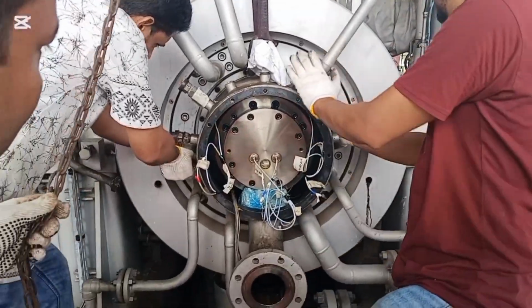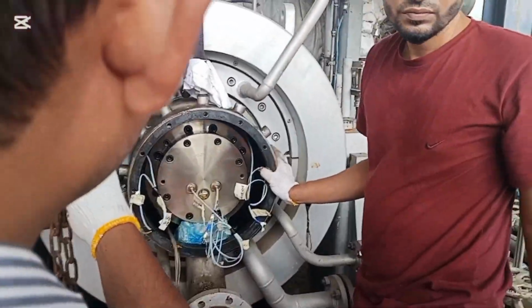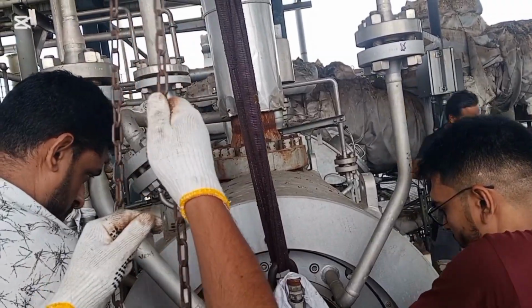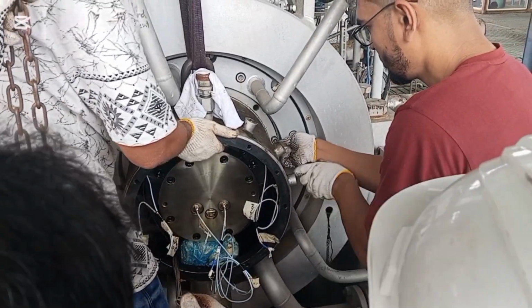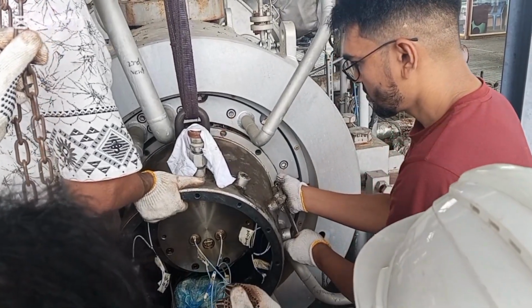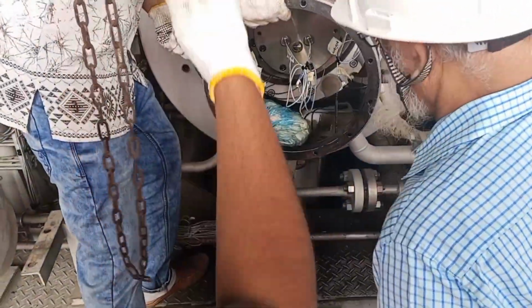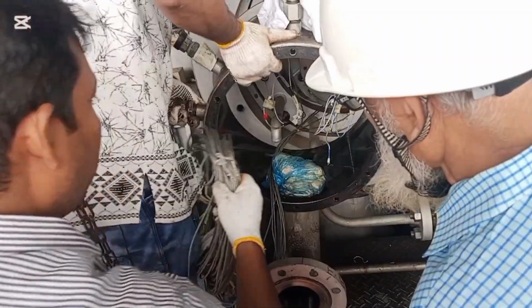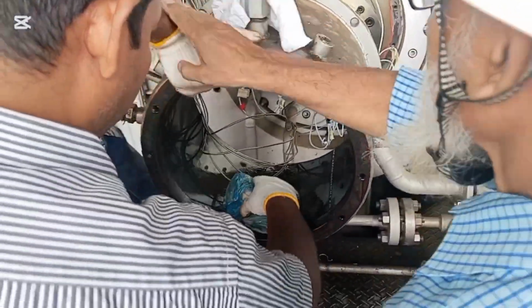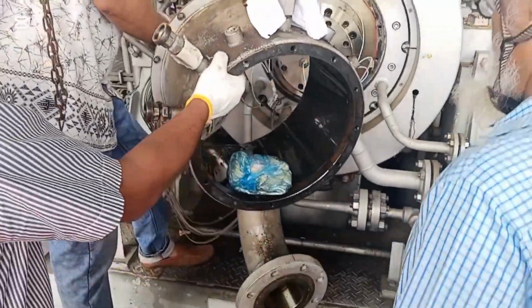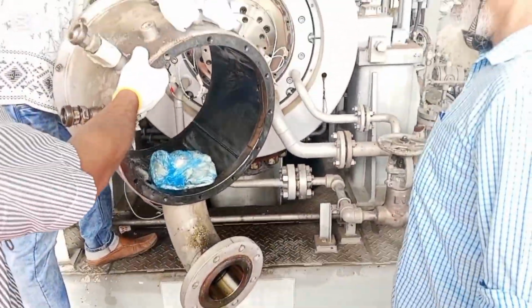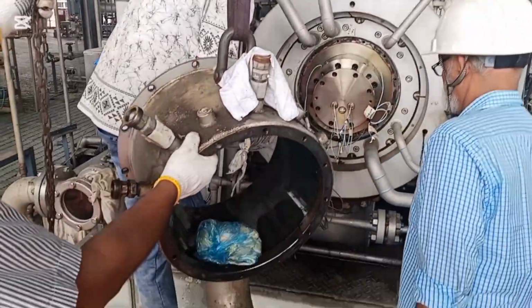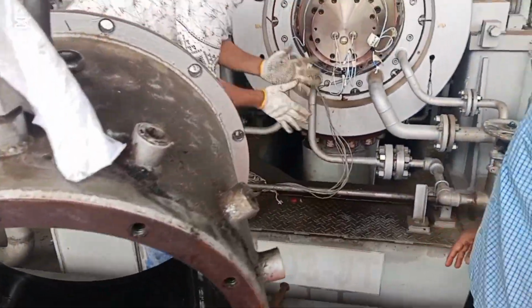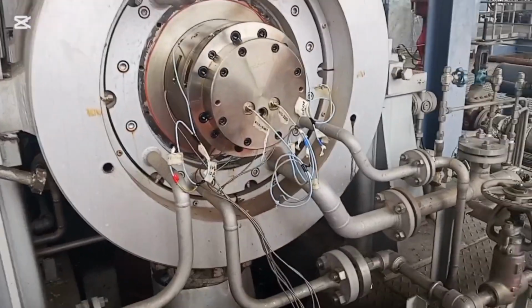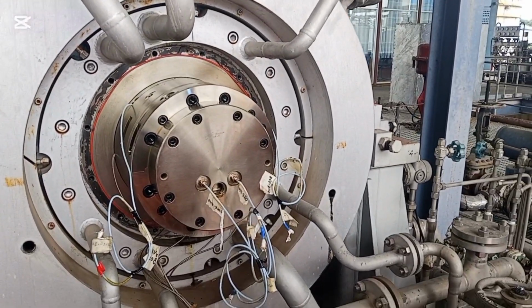After dismantling the instrument cable connections, we opened the mechanical cover and followed one by one for dismantling the unit. Here is some sequence, and we also measured different readings before dismantling the equipment and after assembling the equipment, and they are recorded. Assembling is the reverse procedure of disassembling the dry gas seal at the non-drive end of the syngas compressor, like this.